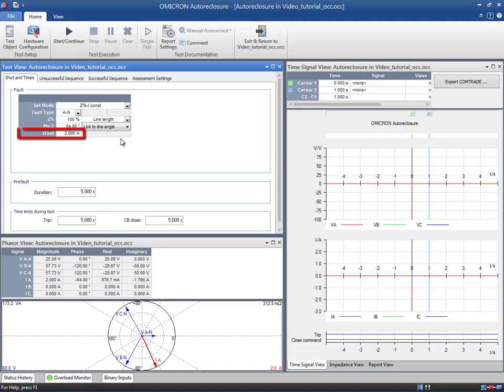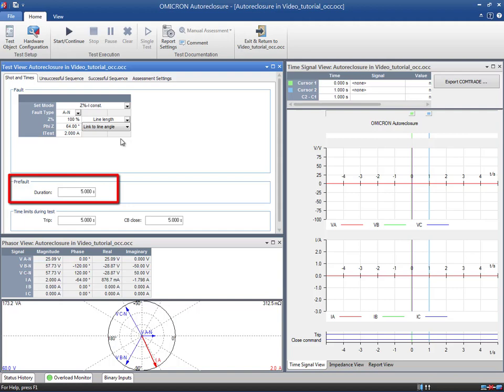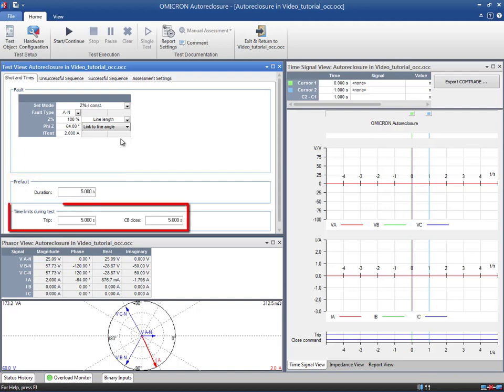Remember that the test current must be above the pickup value of the Distance Protection function. Here you can define the duration of the pre-fault state. This is useful when the Auto Reclosure function presents a blocking time after the last Circuit Breaker Close operation — the pre-fault duration must be greater than this blocking time. With the Time Limits During Test, you can specify the maximum period of time that the module will wait for a trip or a Circuit Breaker Close command, respectively. Keep in mind that the time in the Circuit Breaker Close Entry field has to be higher than the dead time set in the relay; otherwise, the test will be stopped before the relay sends the Close command.